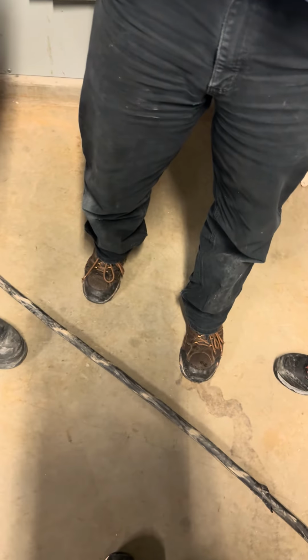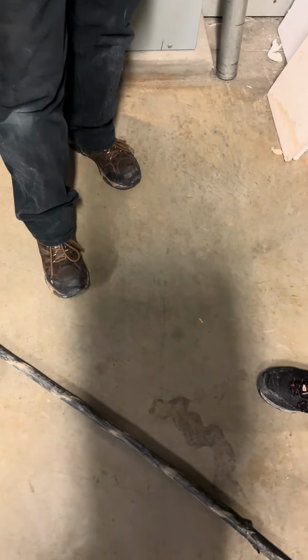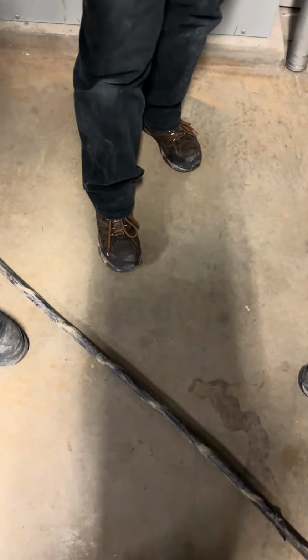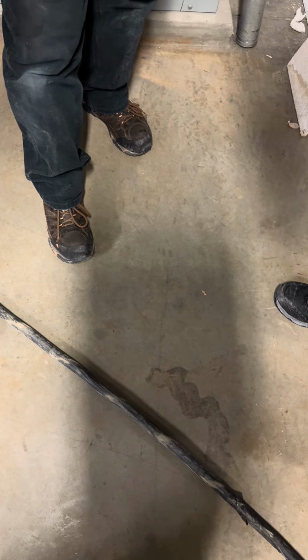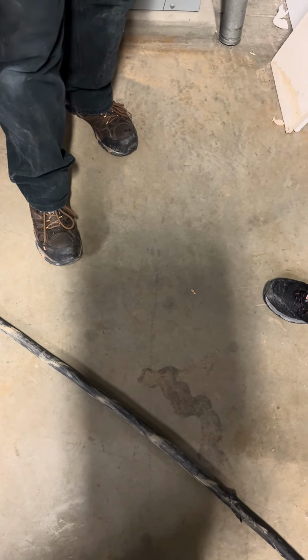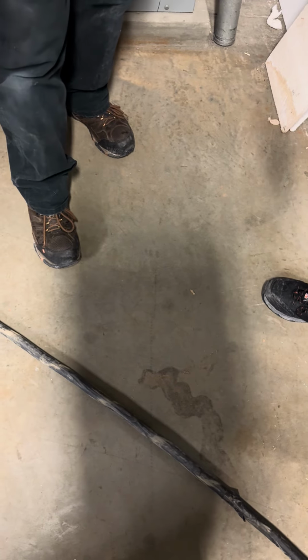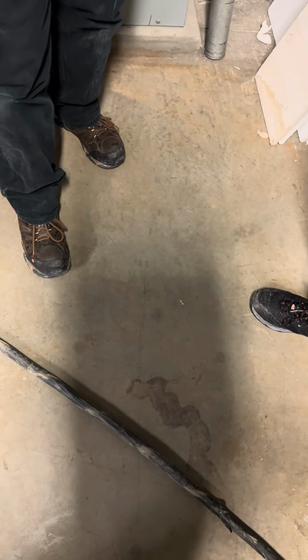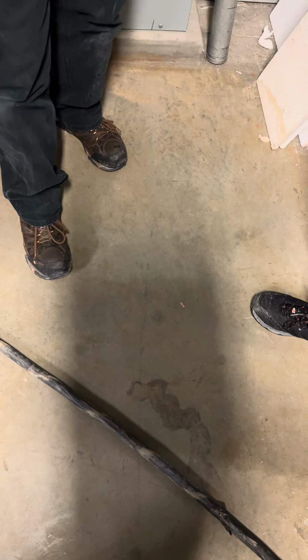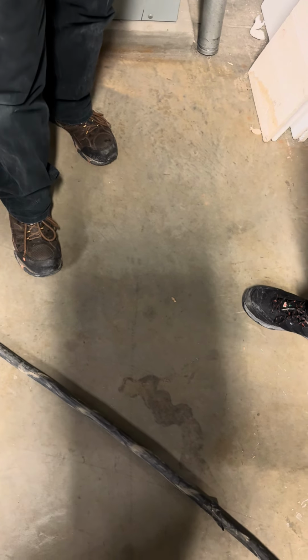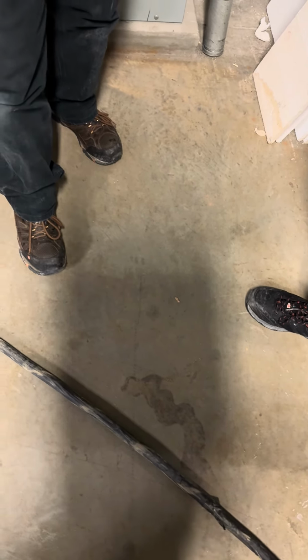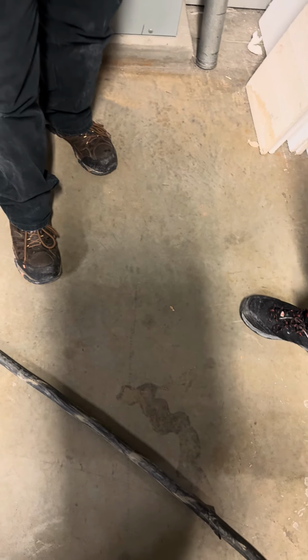In the middle of that VAV box, you can see on the bottom there is an actual rod. The rod is inside where there's a damper that goes up and down. It modulates based on the temperature in the room, and that determines how much air is supplied into the room. Everything is pre-programmed, so when they're building these buildings, they go to the room and say, okay, this is a classroom, or we need this amount of liters per second, and that's all we take.